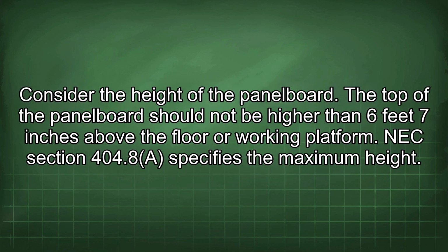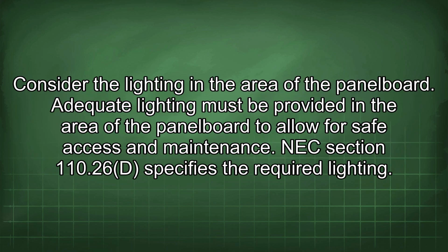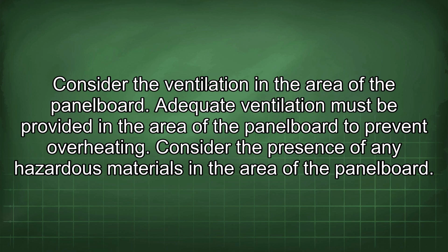Consider the height of the panel board. The top of the panel board should not be higher than 6 feet 7 inches above the floor or working platform. NEC Section 404.8 specifies the maximum height. Consider the lighting in the area of the panel board. Adequate lighting must be provided in the area of the panel board to allow for safe access and maintenance. NEC Section 110.26(D) specifies the required lighting. Consider the ventilation in the area of the panel board. Adequate ventilation must be provided in the area of the panel board to prevent overheating.